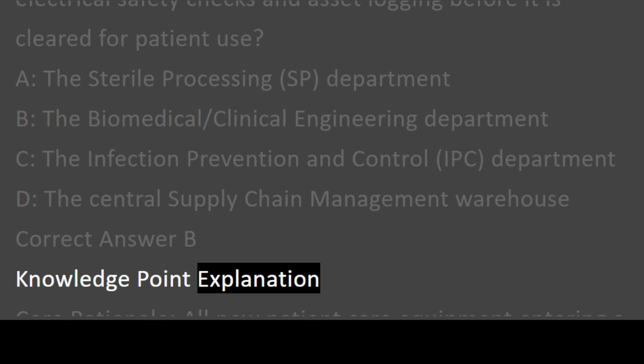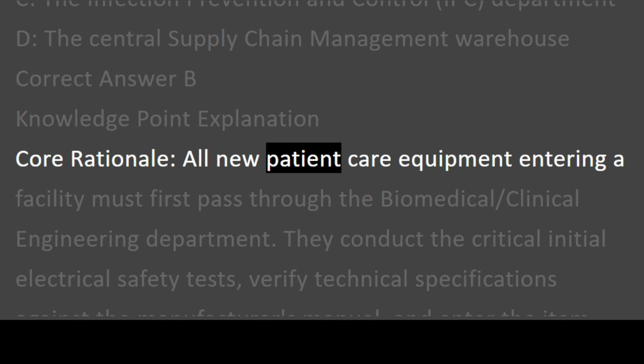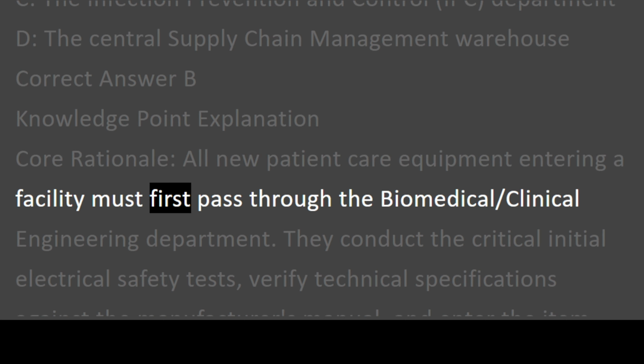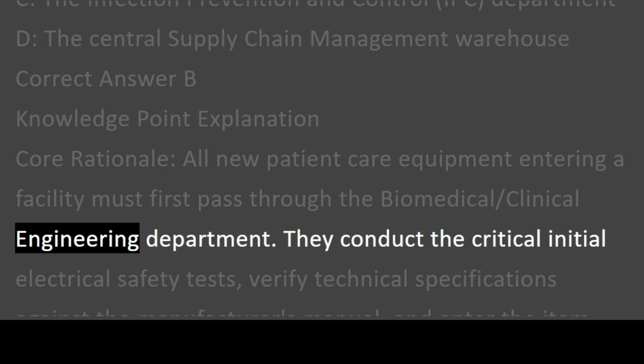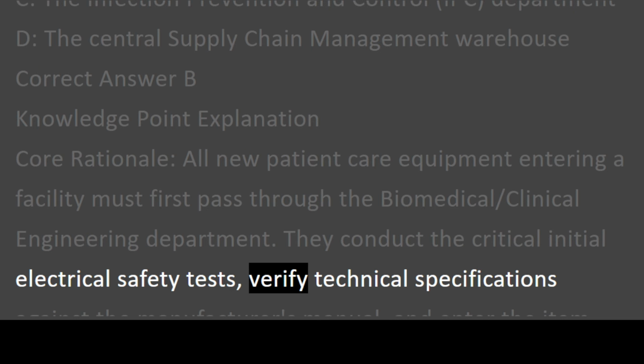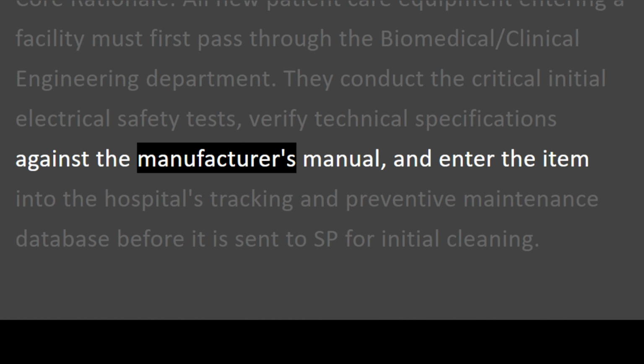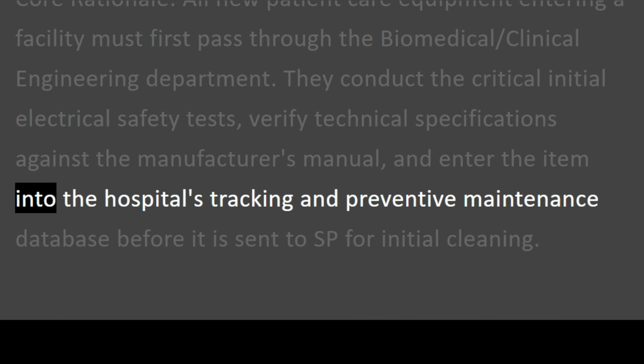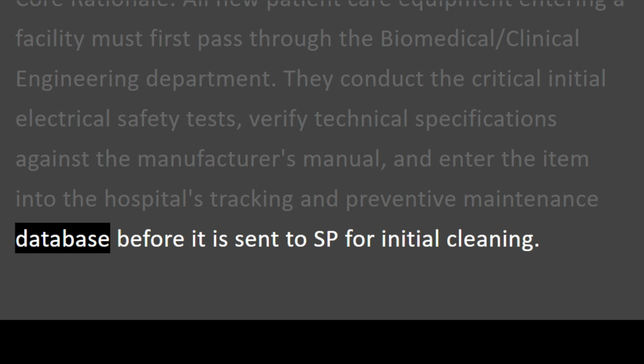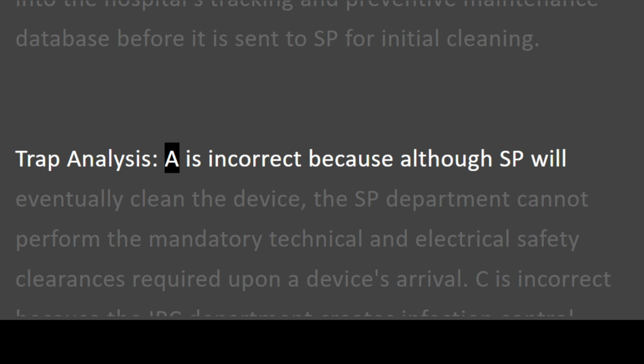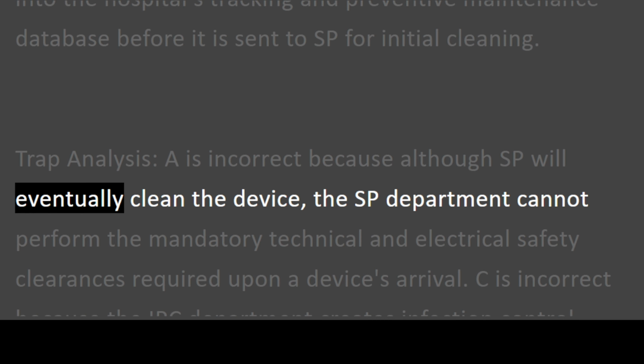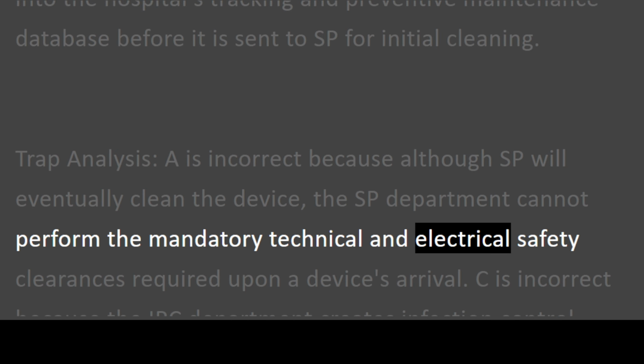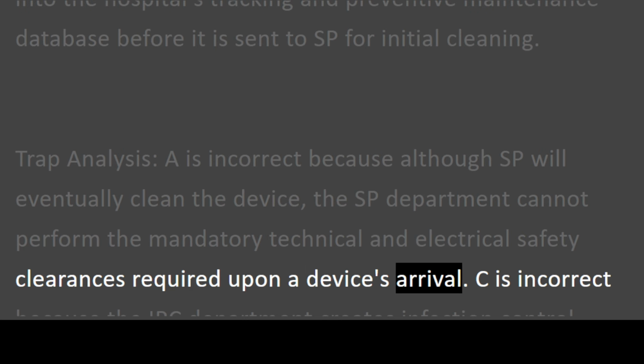Knowledge point explanation. Core rationale. All new patient care equipment entering a facility must first pass through the Biomedical/Clinical Engineering Department. They conduct the critical initial electrical safety tests, verify technical specifications against the manufacturer's manual, and enter the item into the hospital's tracking and preventive maintenance database before it is sent to SP for initial cleaning. Trap analysis. A is incorrect because although SP will eventually clean the device, the SP department cannot perform the mandatory technical and electrical safety clearances required upon a device's arrival.